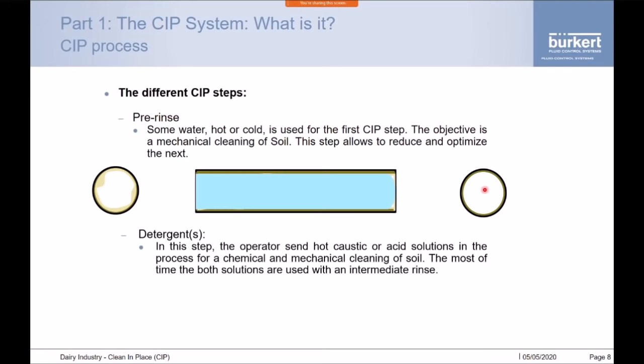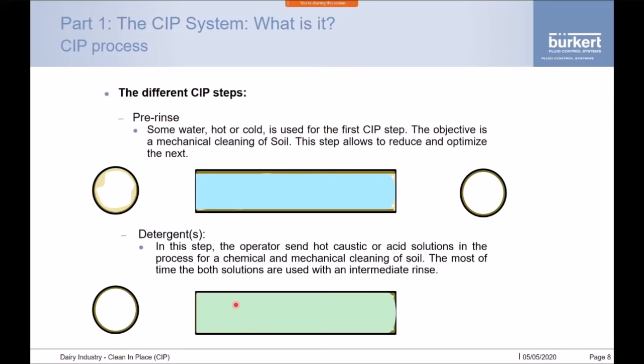We then add the detergent step, where the operator sends hot caustic or acid solutions through the pipework — again at high velocity to maintain mechanical cleaning action as well as chemical cleaning. The detergents remove the large bulk of the remaining material. However, they won't take everything out, so typically after this step we also have a rinse stage to remove any remaining loose particles and chemical left within the pipework and equipment.